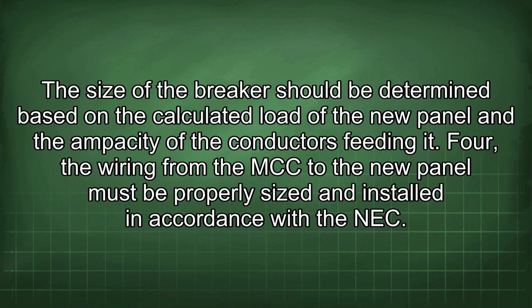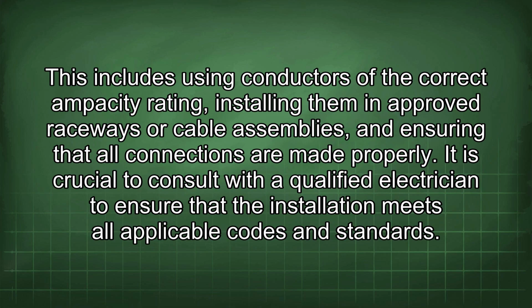4. The wiring from the MCC to the new panel must be properly sized and installed in accordance with the NEC. This includes using conductors of the correct ampacity rating, installing them in approved raceways or cable assemblies, and ensuring that all connections are made properly. It is crucial to consult with a qualified electrician to ensure that the installation meets all applicable codes and standards.